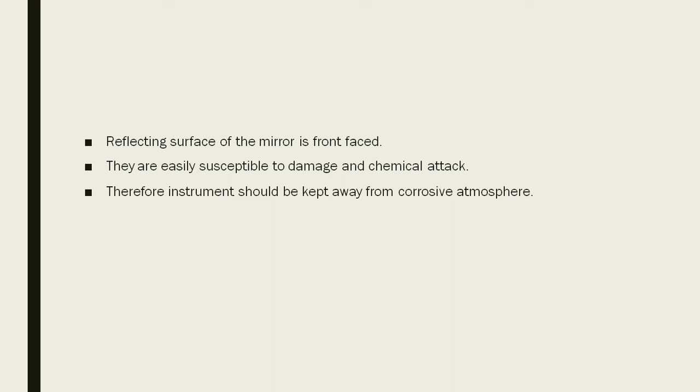Generally, in the mirror which is used in households, the reflecting surface is not front faced, it is behind. So in this mirror which is used in flame photometry, the reflecting surface is front faced.